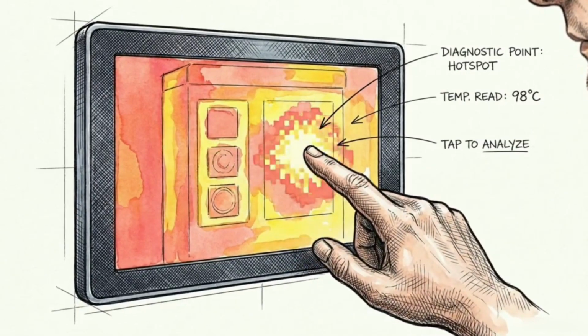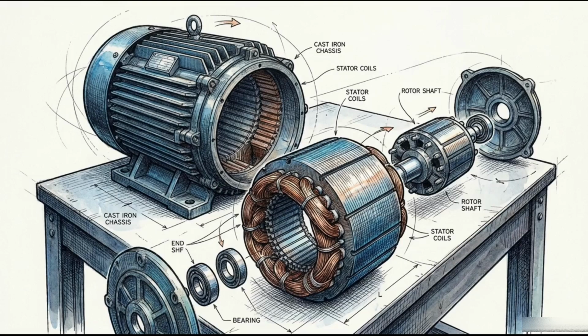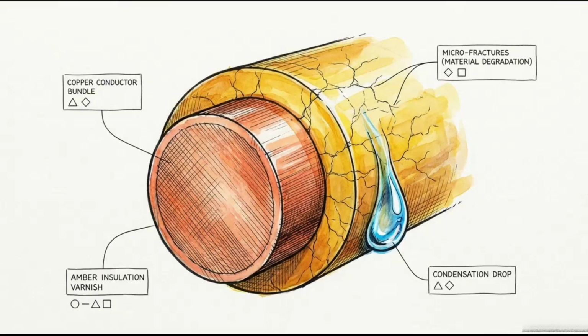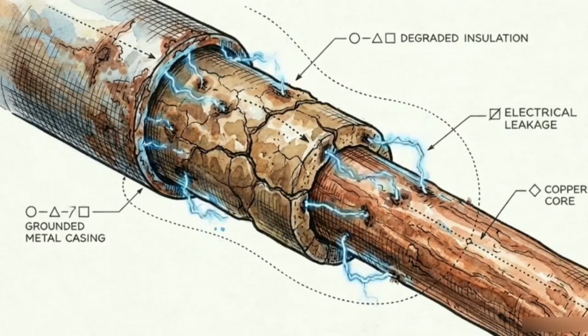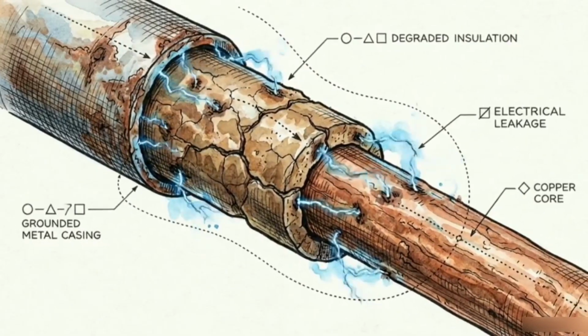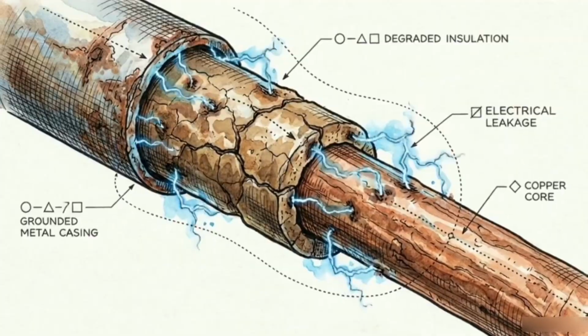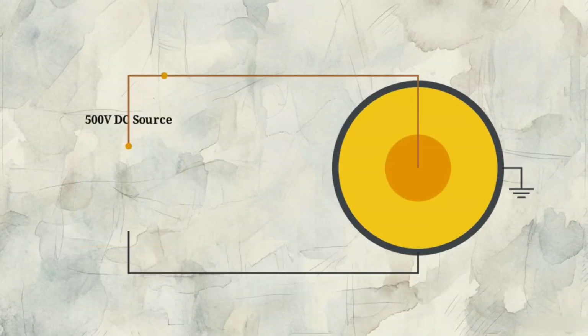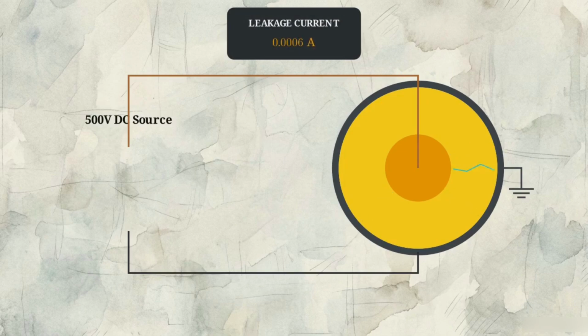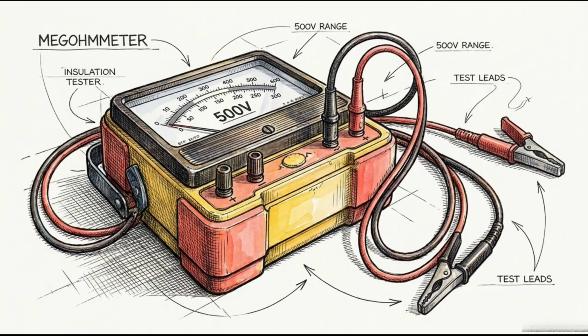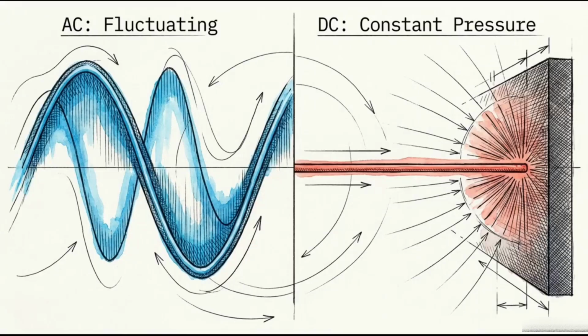While thermal scans catch external faults, we must also audit the internal integrity of the motor itself, specifically the copper winding insulation. This insulation degrades slowly over time due to thermal stress and moisture. As it weakens, microscopic amounts of current begin to leak from the windings to the grounded outer casing. The Megger test quantifies this degradation. By applying an electrical load across the insulation, we can measure exactly how much current is escaping to the casing. This audit requires a stable 500-volt DC source. Unlike alternating current, which fluctuates, a steady DC voltage provides the constant pressure needed to force a readable leak through the barrier. Using Ohm's law, we calculate motor health.